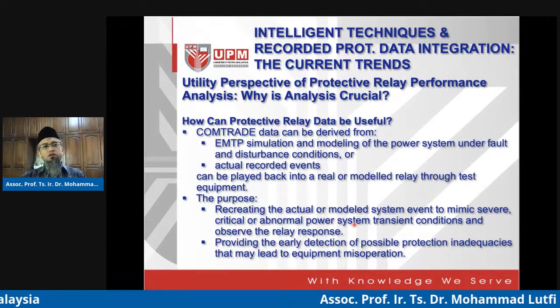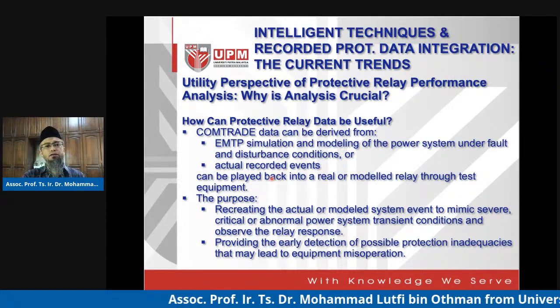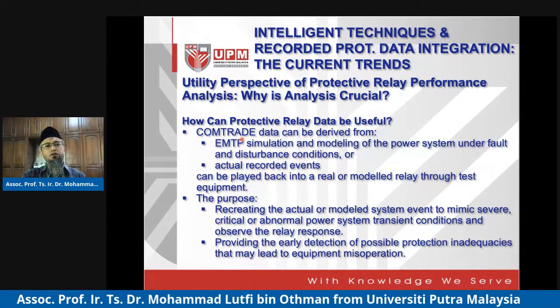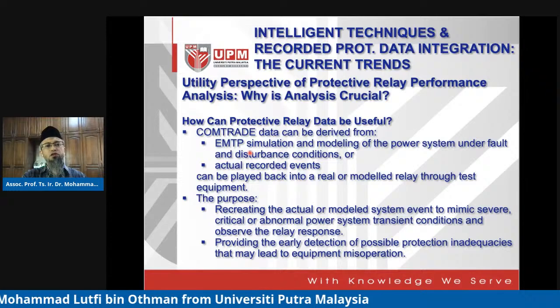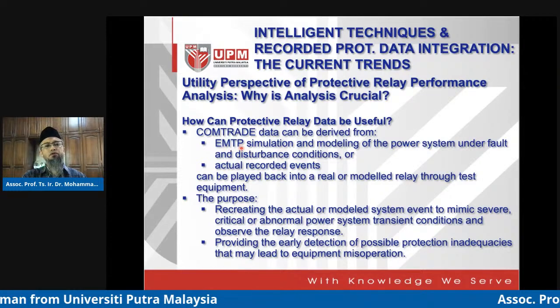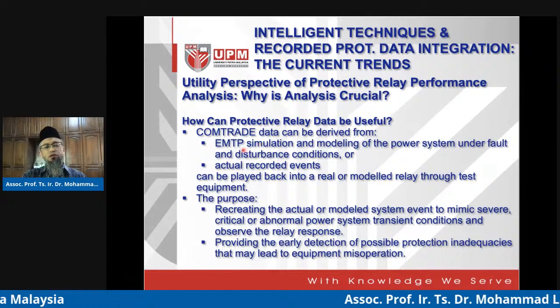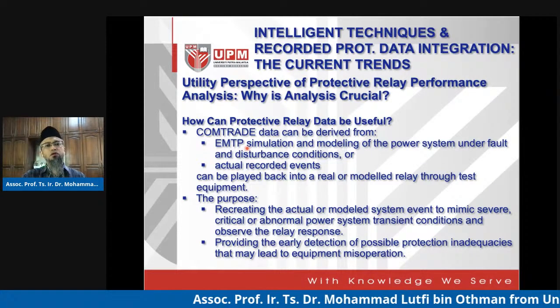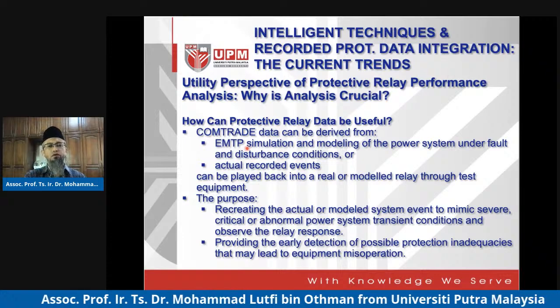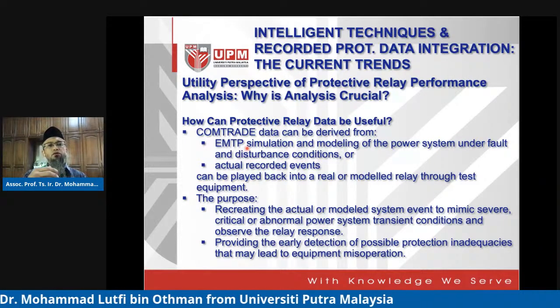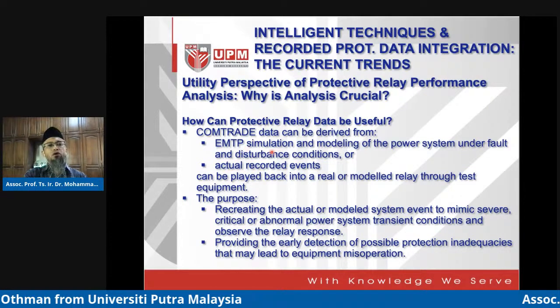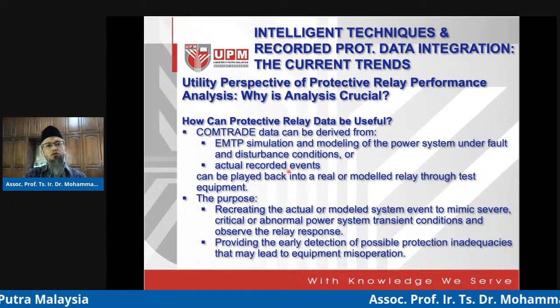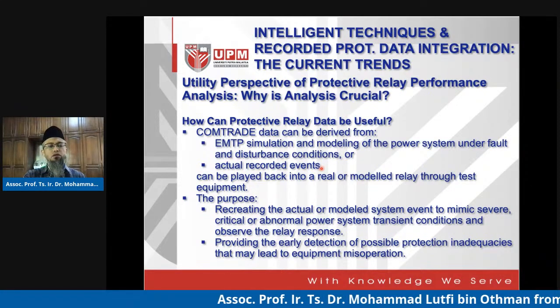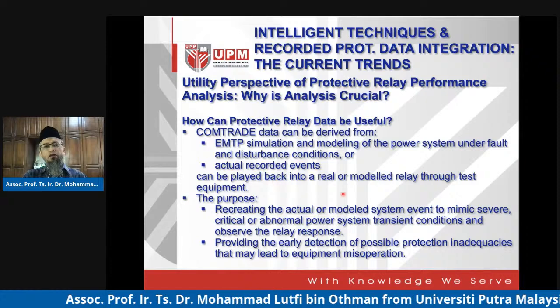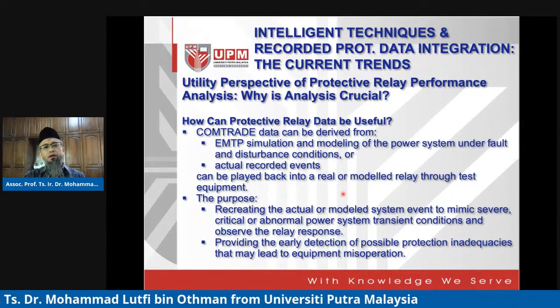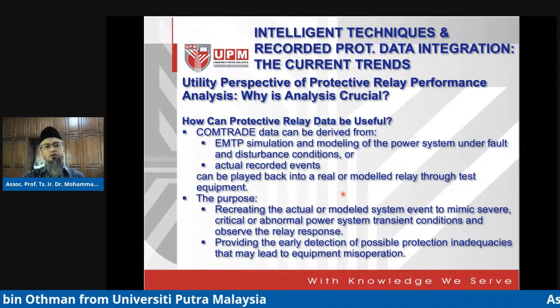Talking about Comtrade, IEEE Comtrade data, you may get this data in one of two ways. You may run a simulation out of the EMTP power simulation tool, electromagnetic transient program tool, running a power system together with protective devices, and then extract the Comtrade data out of it. Or you can get the Comtrade data from actual recorded events from the actual devices at the substations. With this data, you can play it back over the model relay, or even the actual relay found in the substation, to see how they perform.